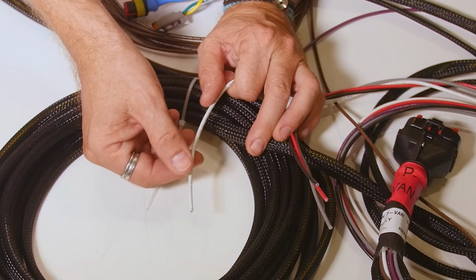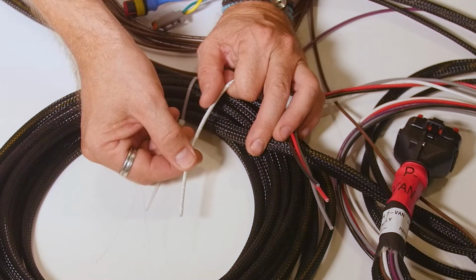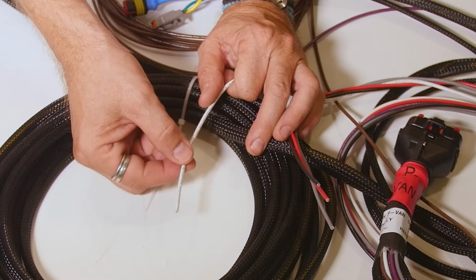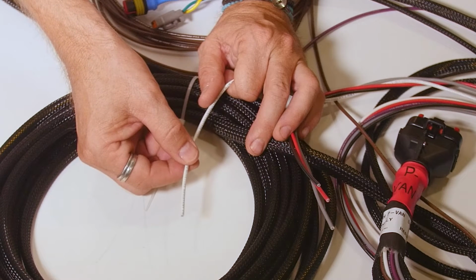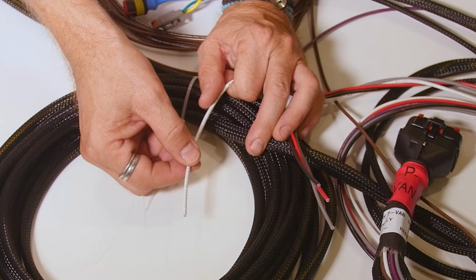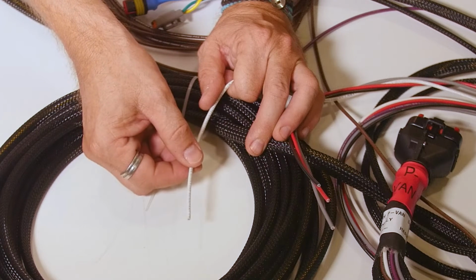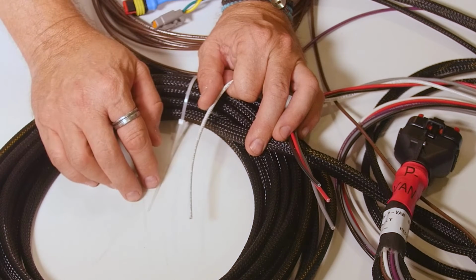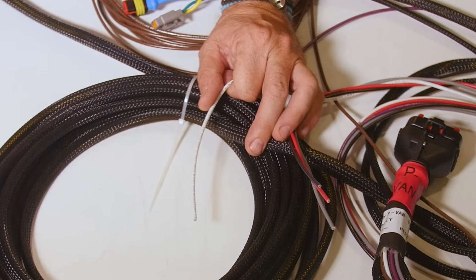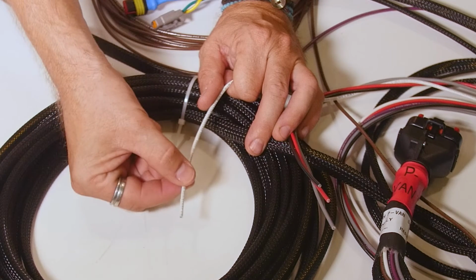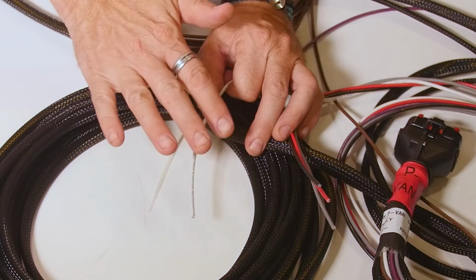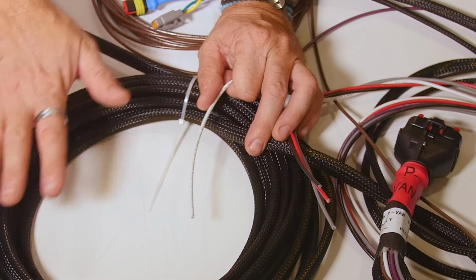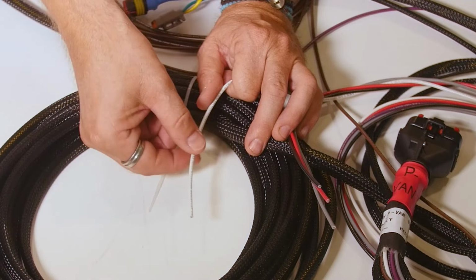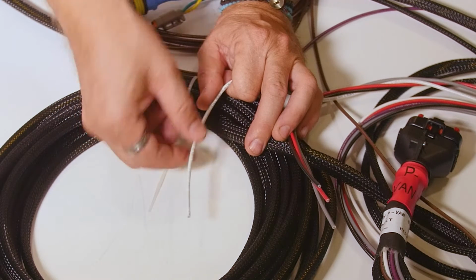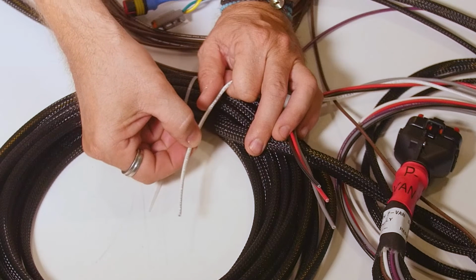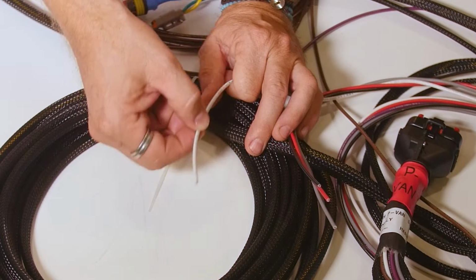In our example power systems, we're using Victron equipment, using the Lynx Smart BMS, and the feature-in wire is a backup to CAN communication around the allow-to-charge circuit. In Victron equipment using external BMS batteries, there's a concept of allow-to-charge and allow-to-discharge circuits. Normally, the Wakespeed is going to be in communication with the system digitally, but if that fails, this feature-in wire connects to the Lynx BMS and allows it to communicate, hey, stop charging, over this analog signal.